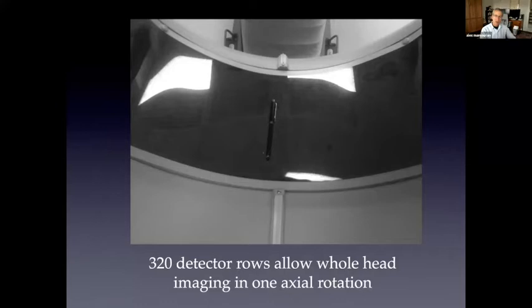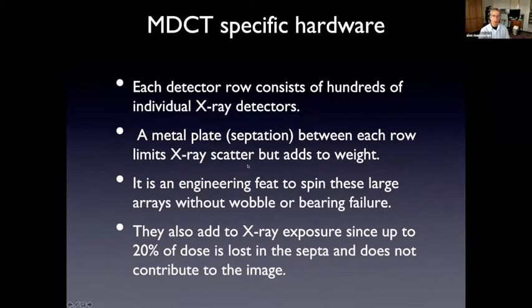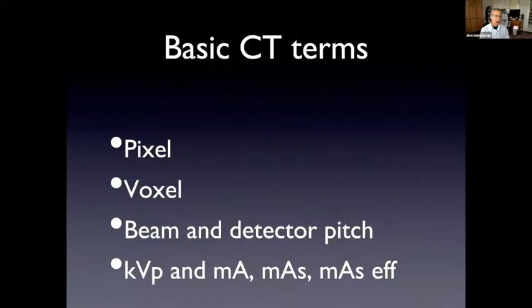But there's some disadvantages to this approach is that a metal plate is used between each row to limit scatter. And this plate or the septation adds weight to the array. So it becomes quite an engineering problem to spin these large arrays without any wobble or bearing failure, and also adds to the x-ray exposure, because up to about 20% of the dose is lost in the septations and doesn't contribute to the final image. So you may think that with modern scanners, we have substantially reduced dose, but in a sense, the opposite has occurred.